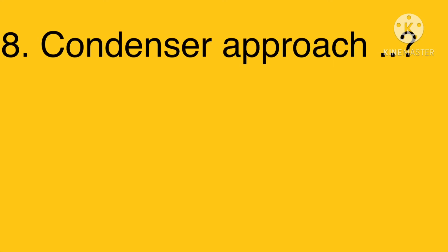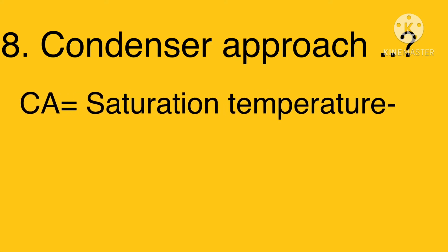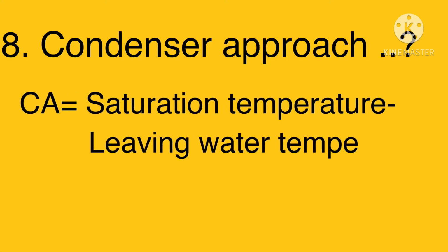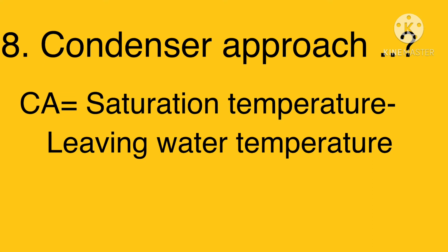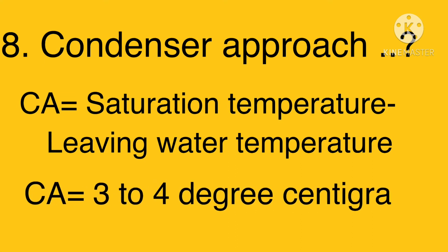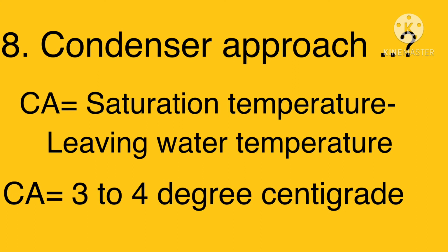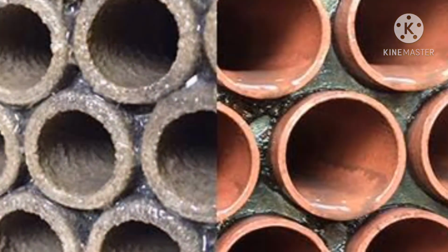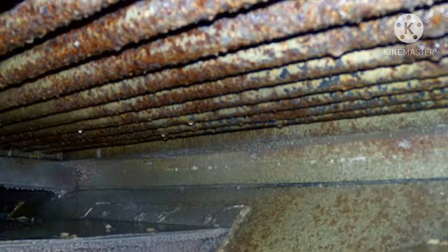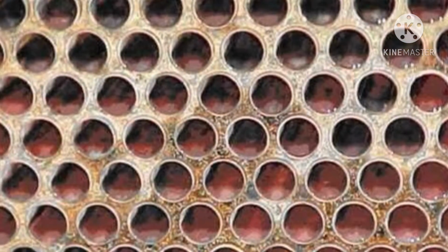What is condenser approach in the chiller system? Condenser approach, CA, is equal to saturation temperature minus leaving water temperature. From a safe operation point of view, the condenser approach should be in the range of 3 to 4 degrees centigrade. Above this value we will get scale formation, and cooling efficiency will decrease.